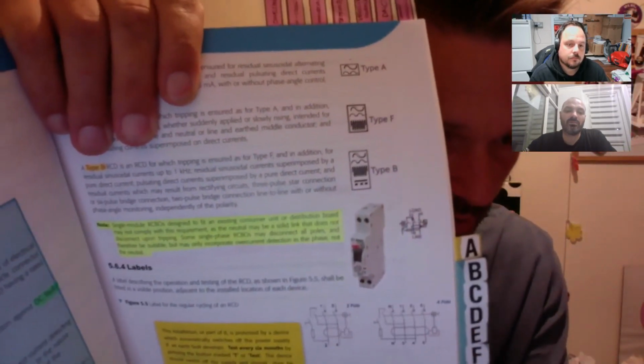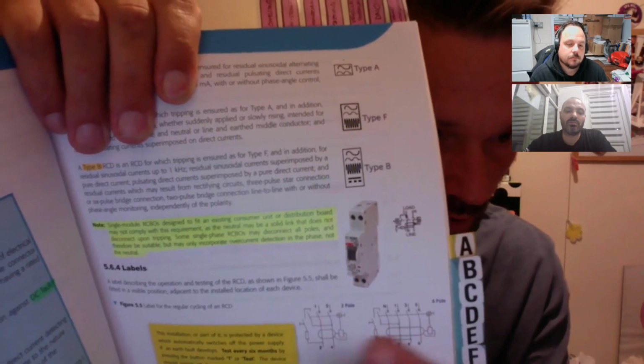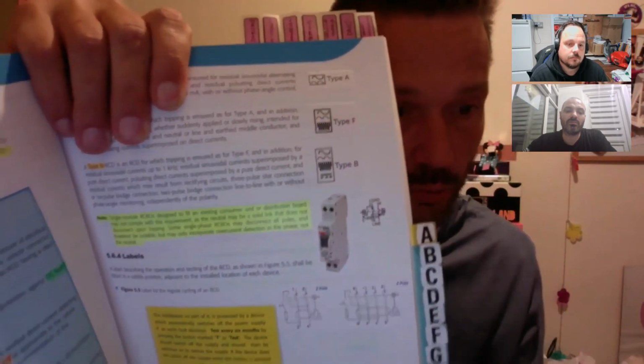On the sides of the RCDs or RCBOs you'll find wiring diagrams which indicate whether they're single pole or double pole, because not all of them are. Some manufacturers need a different product code, so you might think, yeah, it's a Schneider device, best in the business, love Schneider, 60 quid for an RCBO, single pole - no good.